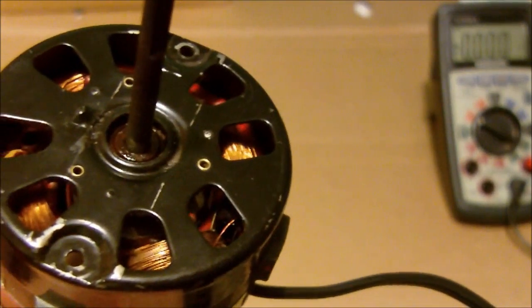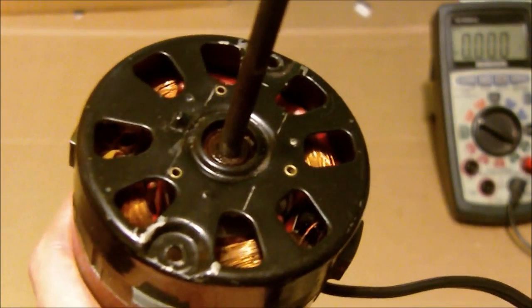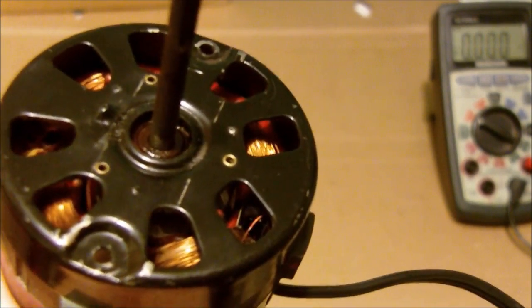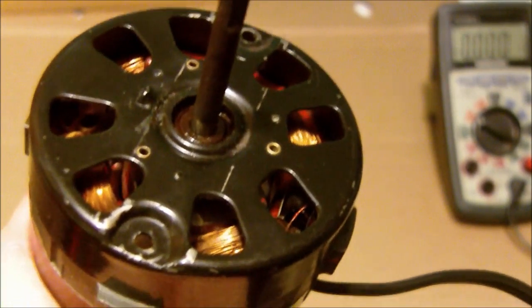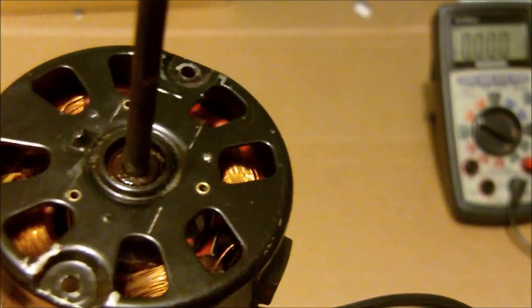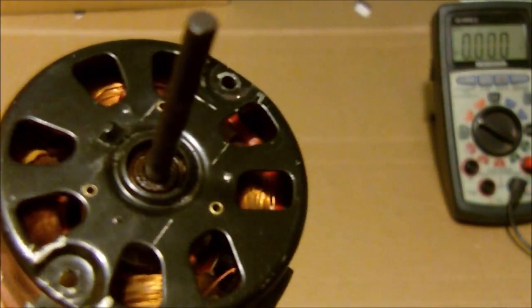And how it's done is with capacitors. They connect capacitors to the output of the actual induction motor. And then if you get the right capacitance and the right RPM, you'll be able to use it as a generator. So an induction motor is not really the greatest for a generator, but they do work.